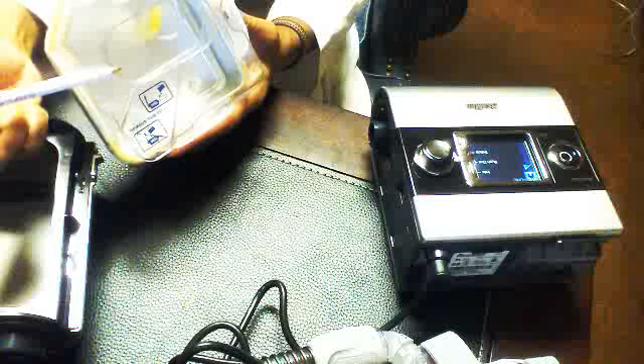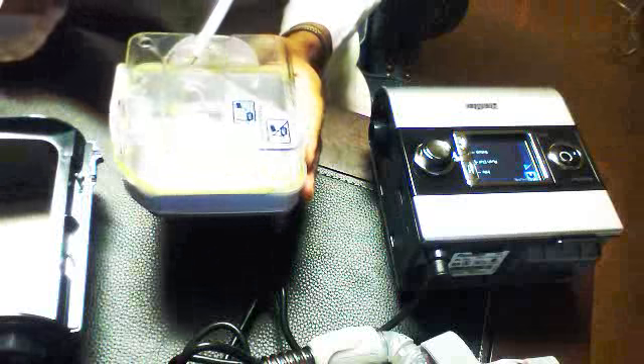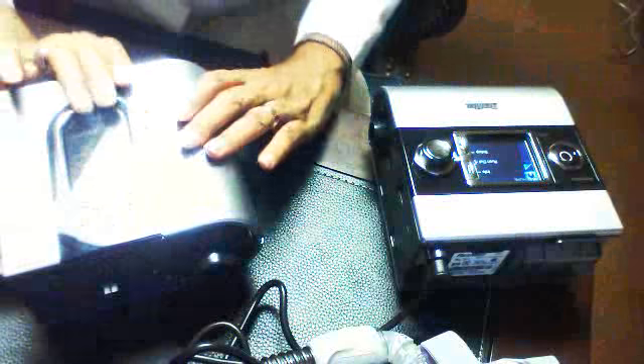When you have your plastic chamber, you'll look and see that it tells you on the inside that you need to be using distilled water with this equipment. Also inside of this plastic chamber is a little yellow tab that tells you where you should stop with your water. It has a water line. It tells you the place to fill, how much water to put into this unit. Once you fill up this water chamber, you pop it back inside your humidifier and close the lid and push it tightly so that it clicks.